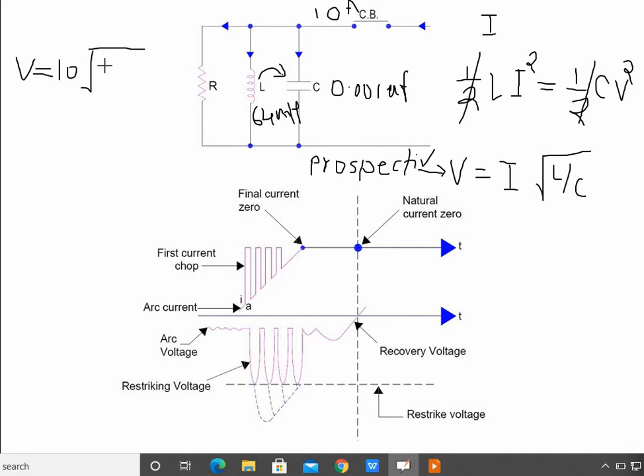The chopping current is 10 ampere. Square root of L, 64 millihenry; we require it in Henry, so 64 into 10 raised to minus 3, divided by C in farad, that is 0.001 into 10 raised to minus 6. If we calculate this value of prospective voltage, it will be say 80,000 volt, or we can write 80 kV.